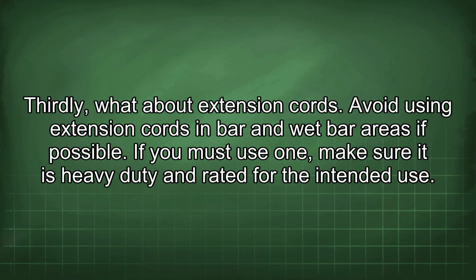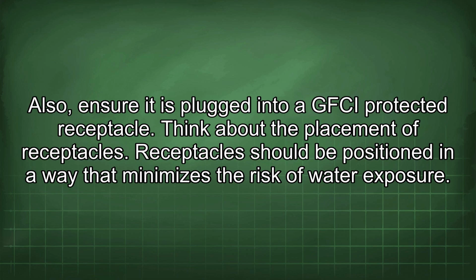Thirdly, what about extension cords? Avoid using extension cords in bar and wet bar areas if possible. If you must use one, make sure it is heavy duty and rated for the intended use. Also, ensure it is plugged into a GFCI protected receptacle.